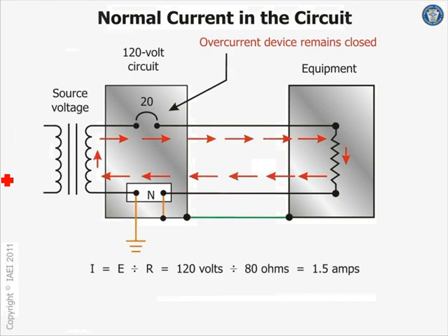Okay, so we have normal operation of the overcurrent device. Look at that, beautifully going, cooking that equipment. Your equipment ground conductor is right here. This is how much current you can pull, based on the impedance of that load: 1.5 amps coming out of a 20 amp circuit breaker. It can go forever without tripping it.